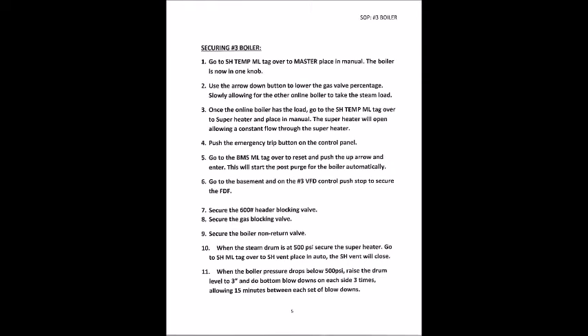Securing number 3 boiler. 1. Go to SH temp ML, tab over to master, place in manual. The boiler is now in one knob. 2. Use the arrow down button to lower the gas valve %, slowly allowing for the other online boiler to take the steam load. 3. Once the online boiler has the load, go to the SH temp ML, tab over to superheater and place in manual. The superheater will open, allowing a constant flow through the superheater.